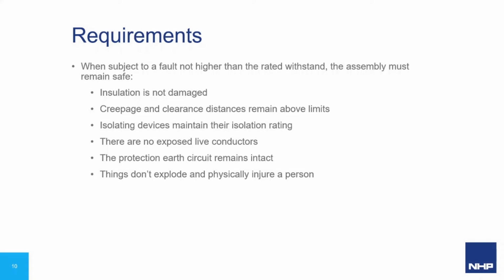So what is meant by withstanding the thermal and dynamic stresses? When subject to a fault not higher than the rated withstand, the assembly must remain safe. This means the insulation is not damaged. Creepage and clearance distances remain above limits. Isolating devices maintain their isolation rating. After the fault, there are to be no exposed live conductors. The IP rating must be maintained. Protection circuit, so the earth, must remain intact, and during the fault, we have to make sure that things do not explode and physically injure a person. It does say that some parts may require service, but the main idea is that our assembly remains safe.